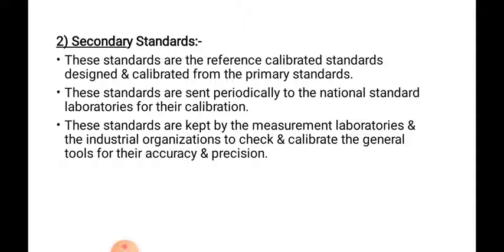The copies of the different primary standards are kept at the international laboratories. The secondary standards are periodically sent to the national standard laboratories for calibration, and it is important. After the calibration they provide the calibration certification for a period of 1 year. On expiry of that certification, the secondary standards are again sent to the national standard laboratories for their calibration.